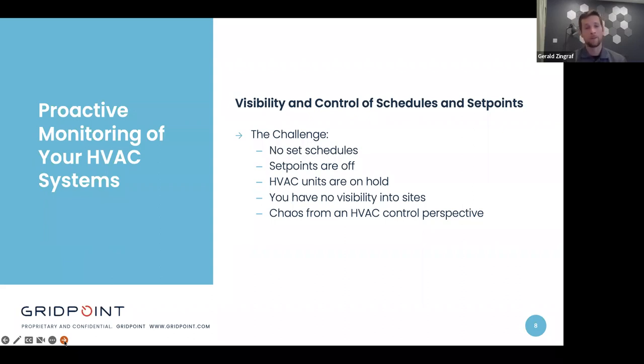Operational drift is very real. So not having set schedules, set points being set to 68 degrees or 74 degrees, often in the same building, HVAC units are placed on permanent hold. The DOE did a study. This is a little outdated now. It was back in 2015. But it showed that 50% of commercial thermostats, or thermostats in commercial buildings, are set to permanent hold.